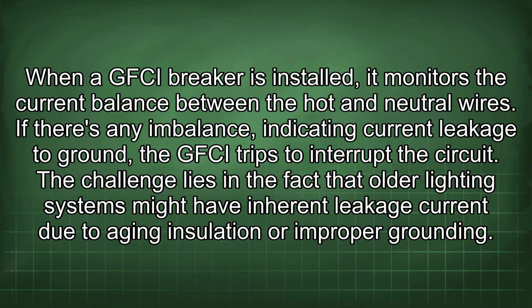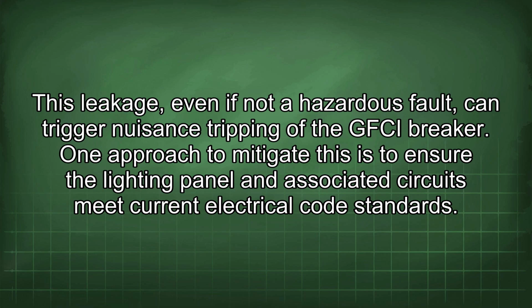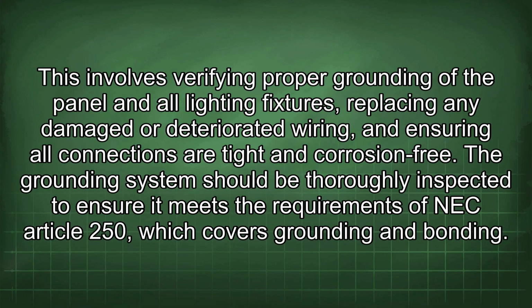The challenge lies in the fact that older lighting systems might have inherent leakage current due to aging insulation or improper grounding. This leakage, even if not a hazardous fault, can trigger nuisance tripping of the GFCI breaker. One approach to mitigate this is to ensure the lighting panel and associated circuits meet current electrical code standards. This involves verifying proper grounding of the panel and all lighting fixtures, replacing any damaged or deteriorated wiring, and ensuring all connections are tight and corrosion-free.